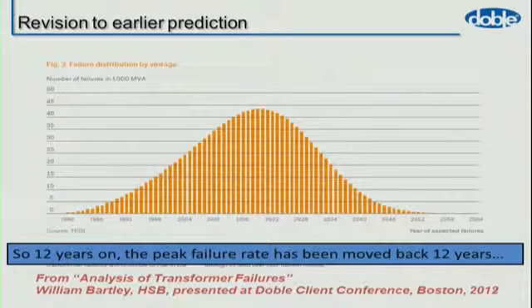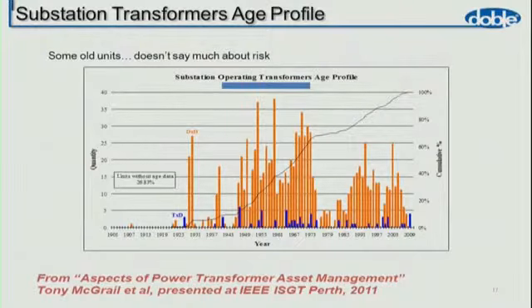Now he's predicting that in 2022 there will be a huge rise in failure rates and we won't be able to cope. But if you compare this, based on his information, with an actual population - this is the number of transformers installed at a utility. The orange is distribution, the blue is transmission, by year. You have transformers going back over 100 years - one from 1907, some from 1920, some from 1928. They're big transformers and they work fine.